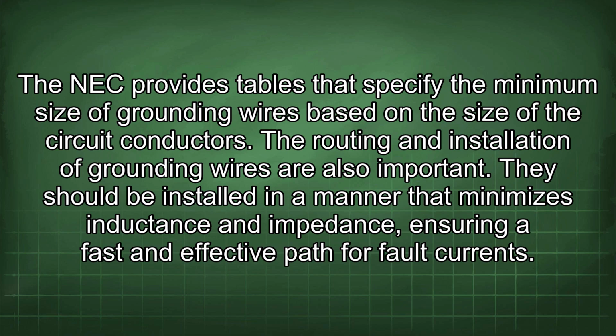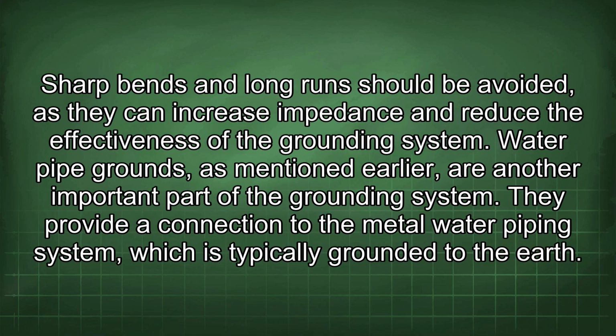The routing and installation of grounding wires are also important. They should be installed in a manner that minimizes inductance and impedance, ensuring a fast and effective path for fault currents. Sharp bends and long runs should be avoided, as they can increase impedance and reduce the effectiveness of the grounding system. Water pipe grounds, as mentioned earlier, are another important part of the grounding system.